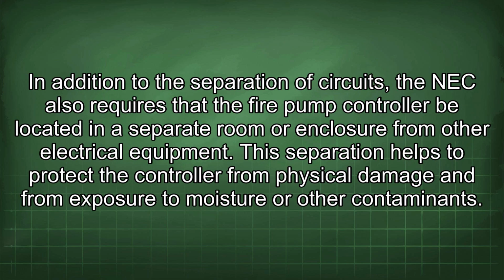down. In addition to this separation of circuits, the NEC also requires that the fire pump controller be located in a separate room or enclosure from other electrical equipment. This separation helps to protect the controller from physical damage and from exposure to moisture or other contaminants.